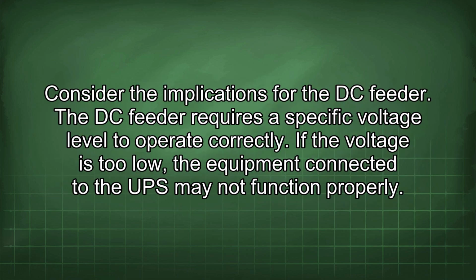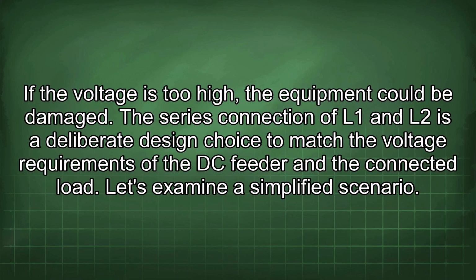Consider the implications for the DC feeder. The DC feeder requires a specific voltage level to operate correctly. If the voltage is too low, the equipment connected to the UPS may not function properly. If the voltage is too high, the equipment could be damaged. The series connection of L1 and L2 is a deliberate design choice to match the voltage requirements of the DC feeder and the connected load.